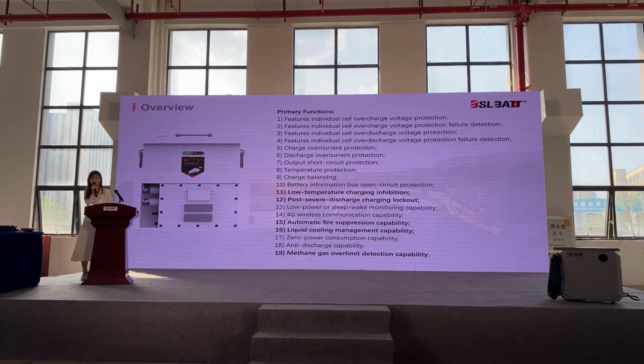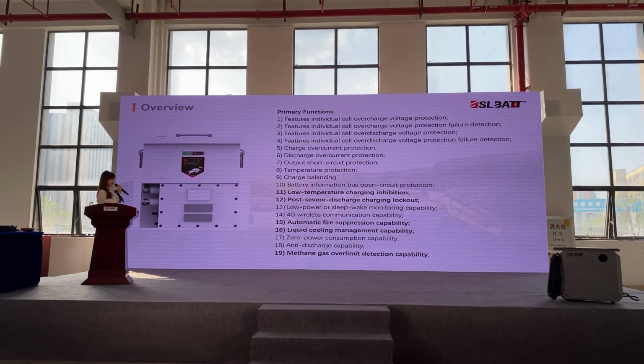For the primary explosion-proof functions, the features are similar to the regular forklift battery, with individual cell overcharge voltage and discharge control by the BMS. What makes it different from the usual forklift battery we manufacture is it has more sensitive low temperature charging inhibition, post-severe discharge charging lockout, automatic fire suppression capability, liquid cooling management, and gas over-limit detection.